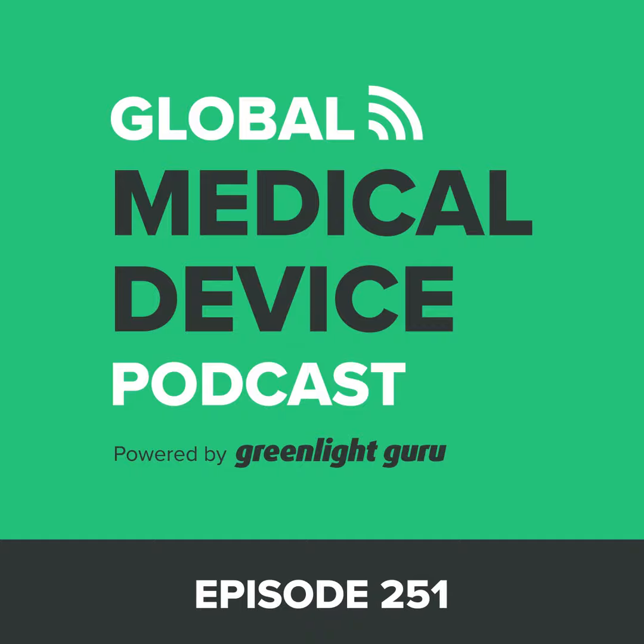Here's all the components. Here's all the parts. Here's the quantity, and here's the supplier. That's actually your device master record. So there's a listing of your device master record, and in some tools it's set by effectivity date. So this is what this DMR looked like. You could say every second of every day as different parts change, you can tell what the DMR is at that point in time.